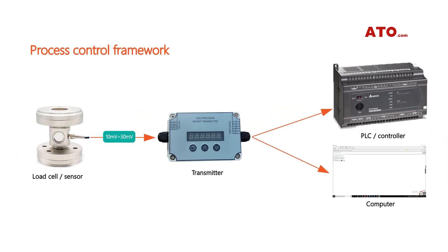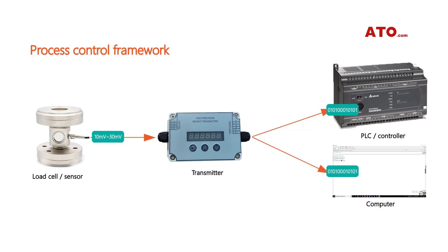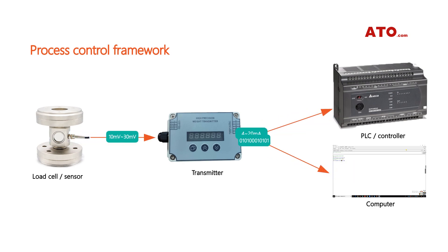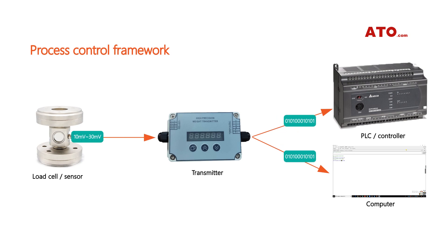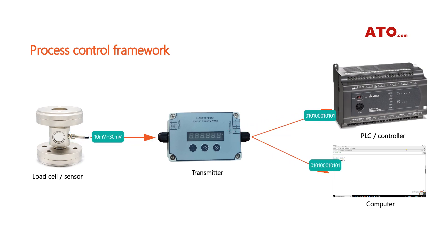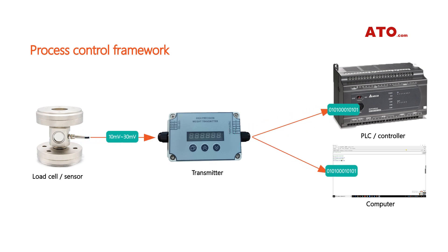The load cell transmits the millivolt signal to the transmitter. Then the transmitter converts the millivolt signal into a 4 to 20 mA standard current signal or digital signal and sends it to the PLC or computer. The computer or PLC communicates with the transmitter through the Modbus protocol and translates the digital signal into a decimal number that can be recognized.